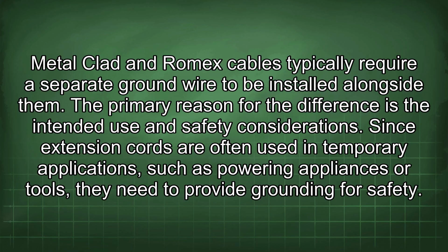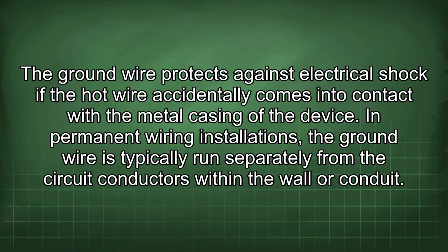The primary reason for the difference is the intended use and safety considerations. Since extension cords are often used in temporary applications, such as powering appliances or tools, they need to provide grounding for safety. The ground wire protects against electrical shock if the hot wire accidentally comes into contact with the metal casing of the device.